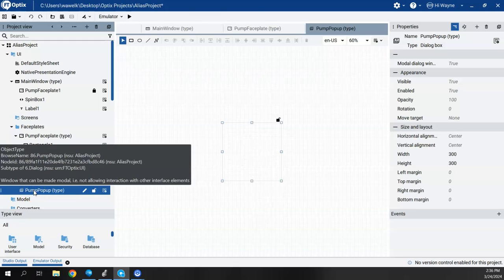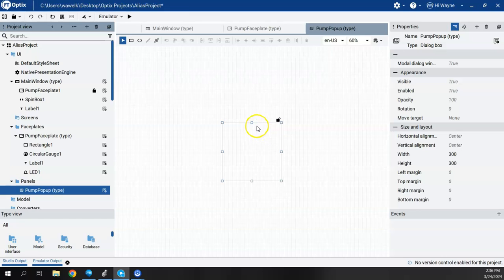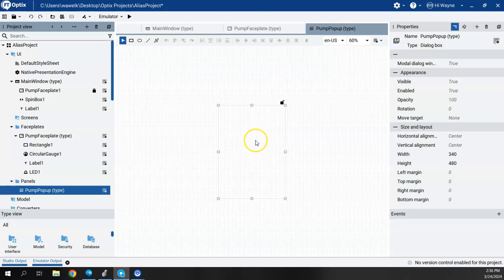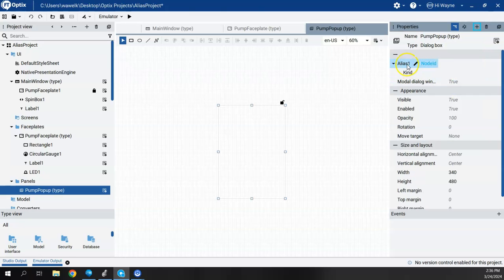Double-clicking on pump popup, it's a blank canvas right now. I'm going to stretch it a little bit bigger and make it a bit wider to give myself enough room to add the pump faceplate widget. Before I do that, there are a couple of things to set up. First, we need to create an alias for this pump popup. With it highlighted, I'll go to properties and press add new, select alias. I'll call it pump popup alias.